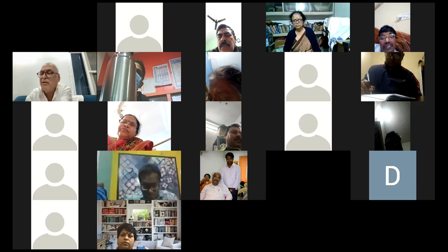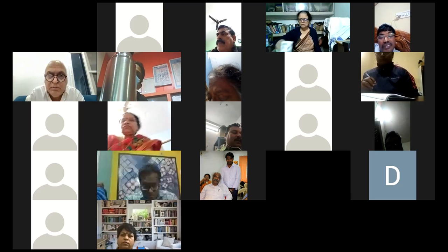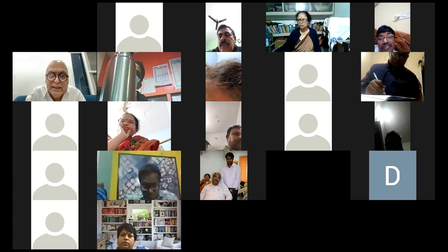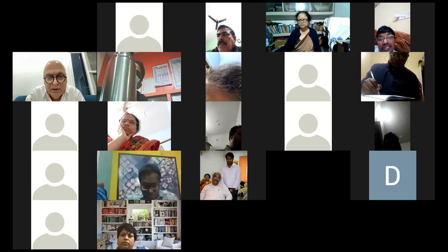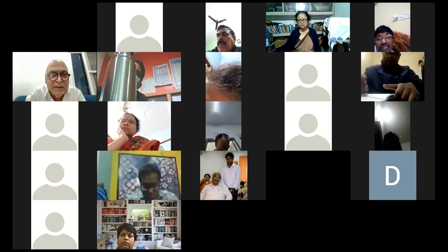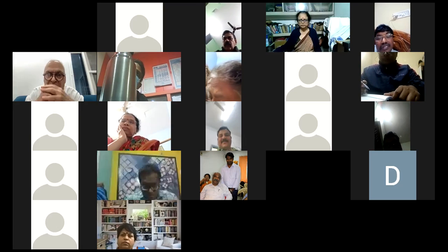The first button you are going to use is the depth. The second one is the sector. Third one is focus. Anybody can tell me whether there is a direct button to reduce the field of view or expand the field of view? No sir, I think it must be adjusted. You have to adjust the sector. In all machines there is a sector button. That is also sometimes called the angle.